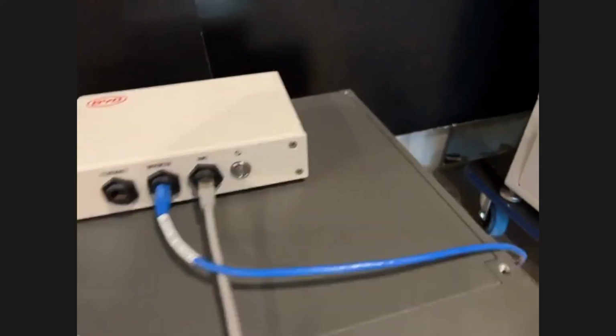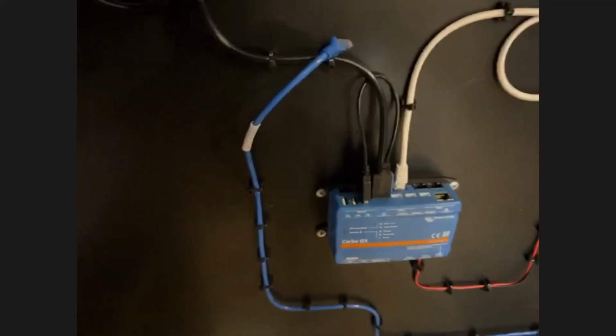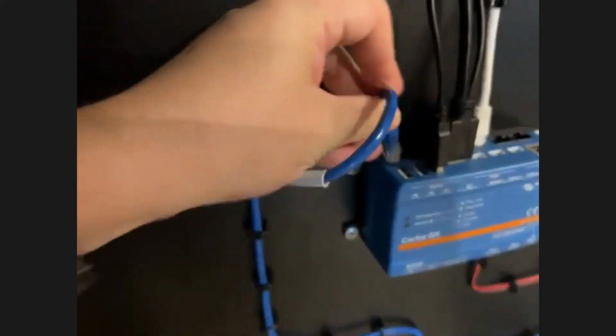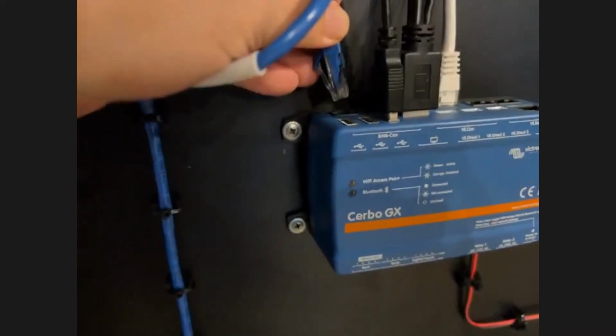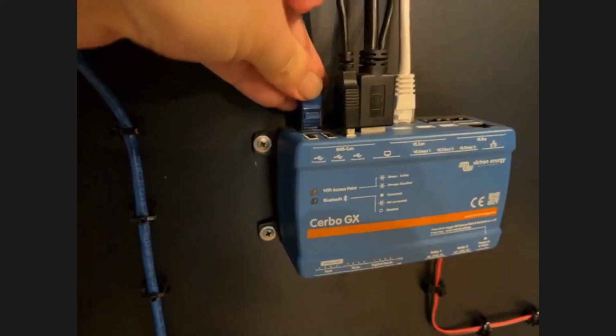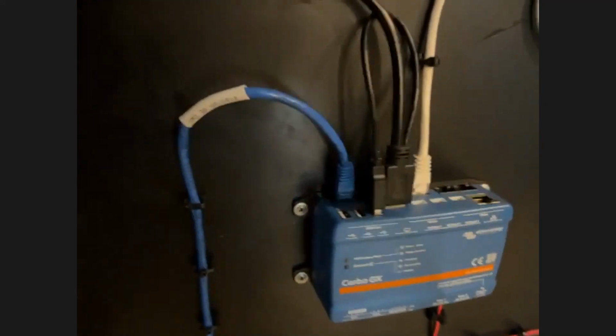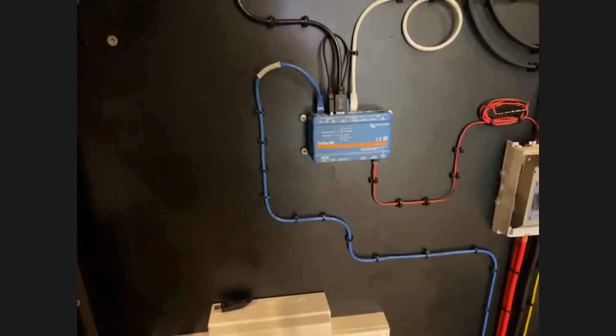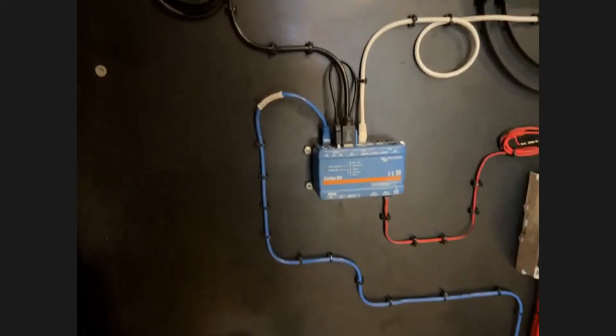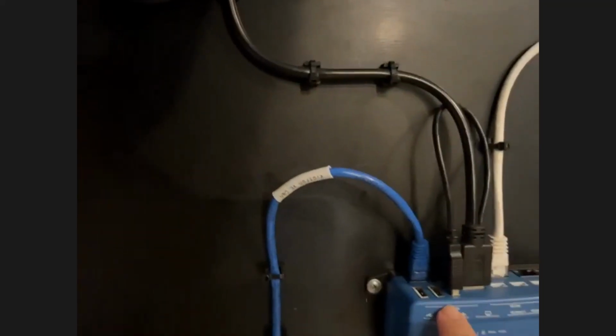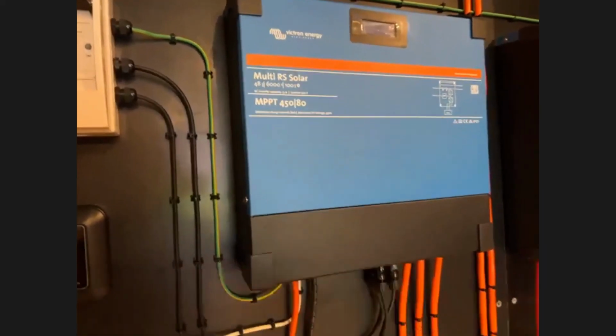I'm now going to follow this blue comms cable around up to our Cerbo GX, which is up here, and we're going to connect it into the BMS CAN ports here. These BMS CAN ports come pre-configured by default at the baud rate required by the BMS or BMU of the BYD system, so that's the right port to use. In this case, the VE.Can is connected through to my inverter charger up here.